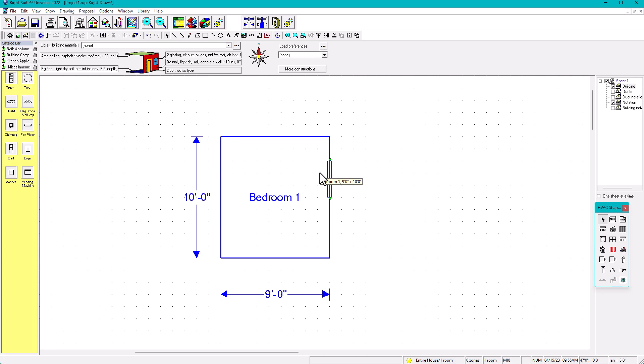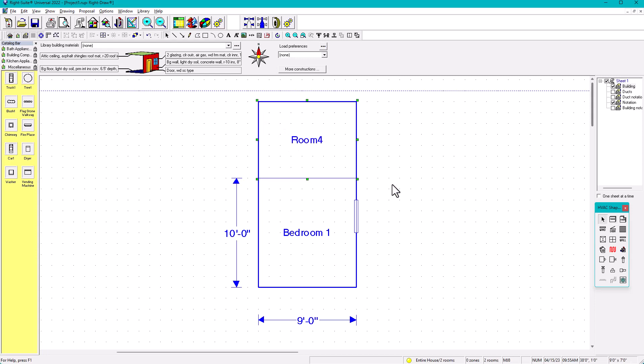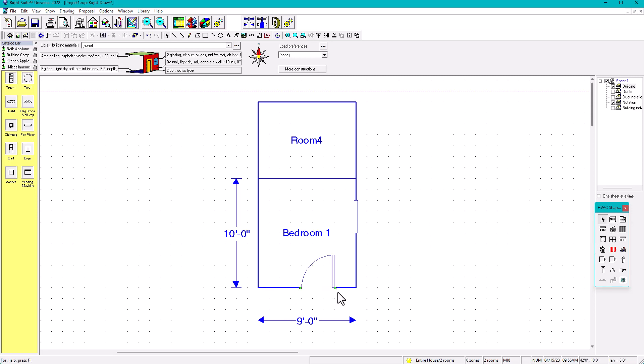What if you have a partition? Let's add another room adjacent to this one. Notice that everything exposed is shown with bolded lines, but the shared interior wall between the two rooms is thinner — that means it's a partition wall. Partition walls are conditioned, so they don't matter for heat load calculations. Only exposed walls are important.